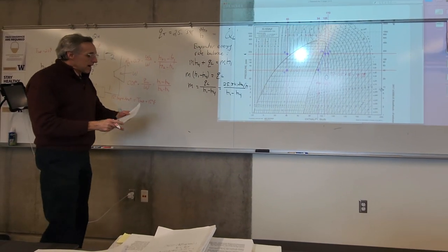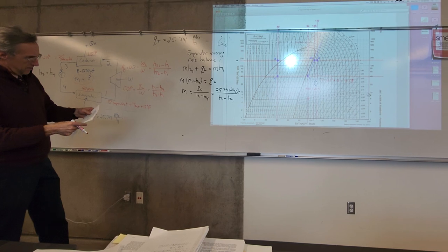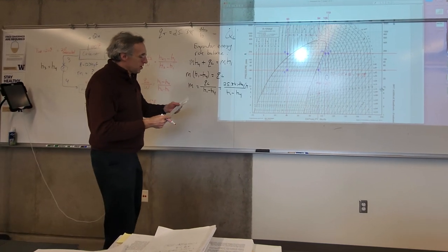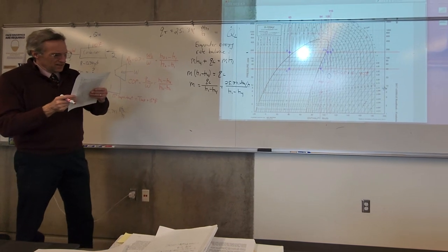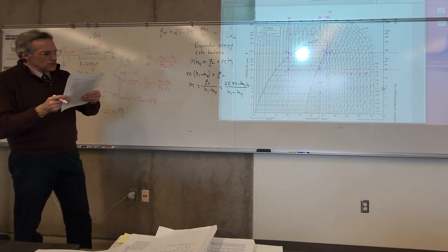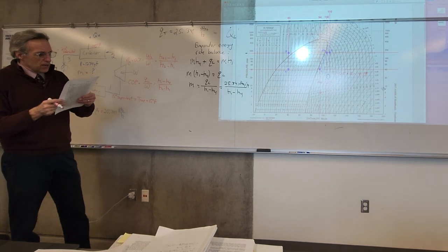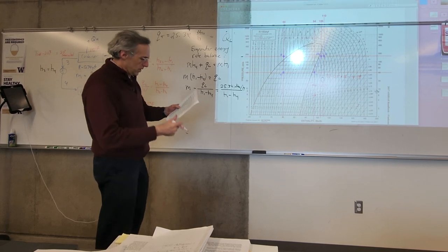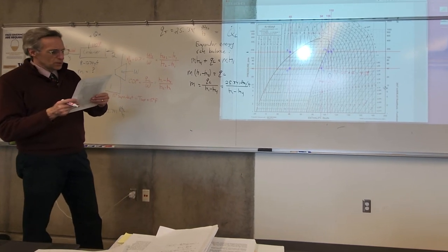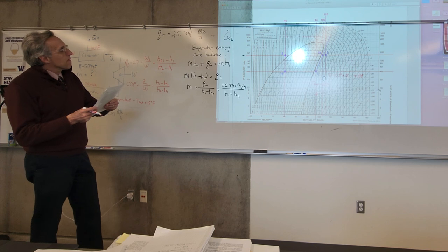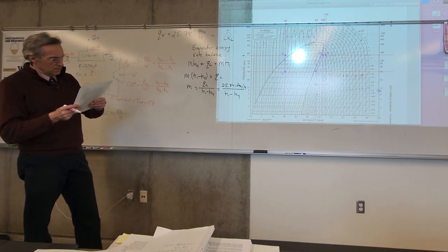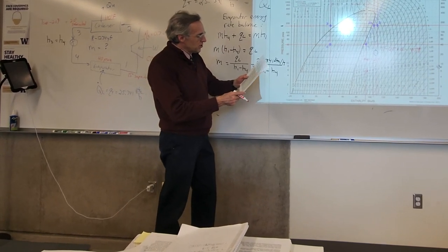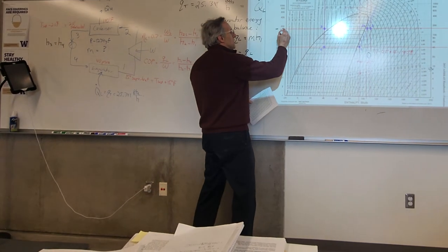And again, to get exact, I go to the back page. Let's see, if we're at 110 degrees, so if I go to 110 degrees, it's gonna be close to 85 degrees, right? It's about 84. Oh, wait a second. No, I'm reading this wrong. What am I doing wrong here? I think if you go to temperature for 110, yeah, and temperature then you read is the pressure. Oh, okay. So the pressure, I go to 110 degrees, and the pressure is about 160, 161.